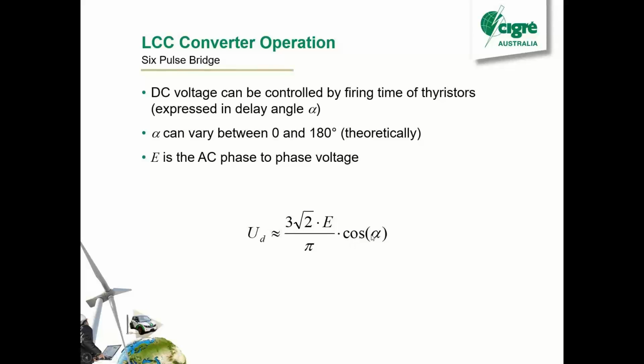And then as you increase alpha, you'll be able to reduce your voltage. When we're operating at 350 kV, our alpha is usually about 16 degrees. But if we want to go to 250 kV, we increase it up to about 30, 35 degrees. So that shows you how you've got your control over the voltage there.